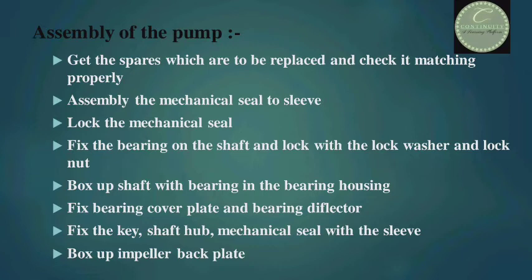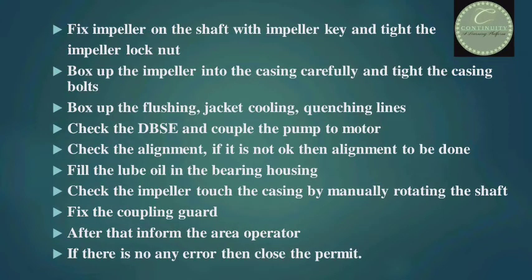Steps involved in the assembly of the centrifugal pump: Get the spare parts to be replaced and check they match properly. Assemble the mechanical seal to the sleeve and lock it. Fix the bearing on the shaft and lock with the lock washer and lock nut. Box up the shaft with bearing in the bearing housing. Fix the bearing cover plate and bearing deflector. Fix the key, shaft hub, and mechanical seal with the sleeve.